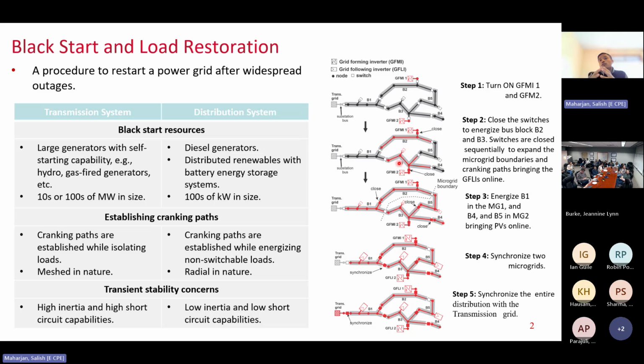Basically, your grid forming inverters are helping to form a microgrid, and these microgrids help energize the neighboring bus block at a time so that they can bring the grid following resources online. These grid following resources will augment the power and energy capacity of the grid forming inverters, helping them to restore more loads. Then after that, the switching is again conducted independently at different microgrids to restore the loads as well as to bring the grid following DERs online, right?